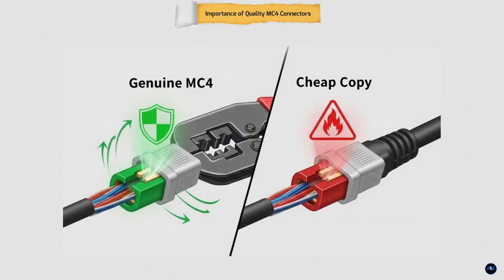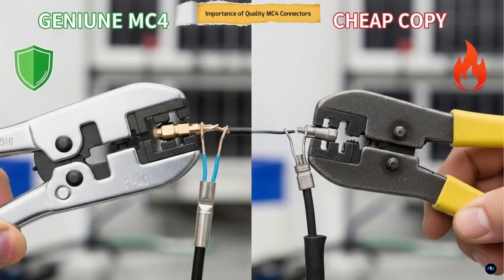Importance of quality MC4 connectors. Never underestimate your connectors. Always use genuine MC4 connectors, properly crimped with the correct tool. Cheap or mismatched connectors are one of the most common causes of DC fires. Avoiding voltage drop final tips. As a general rule, aim to keep DC voltage drop below 2 to 3%. Shorter cables, thicker conductors, and solid connections all help. Good wiring doesn't just improve efficiency, it protects your system for years.